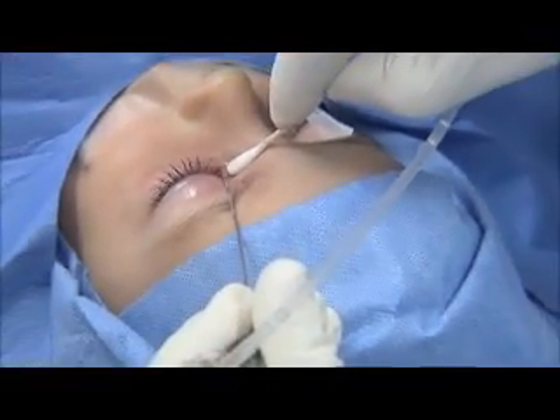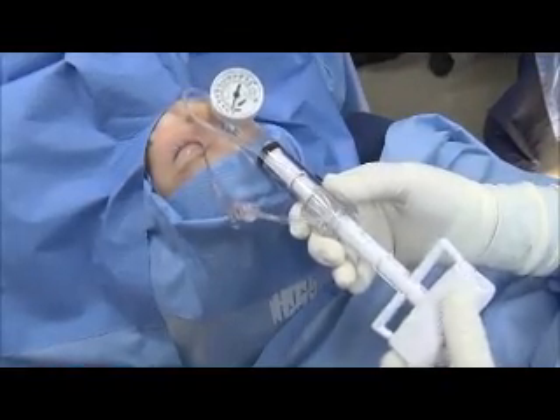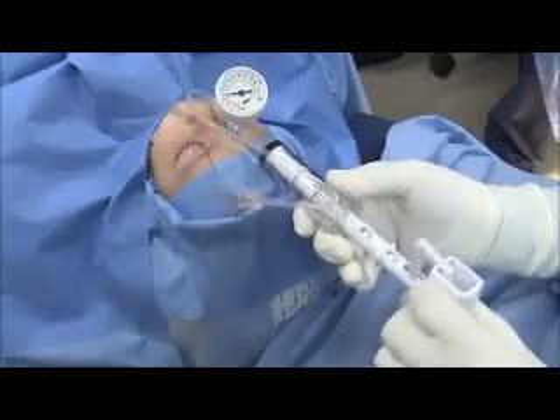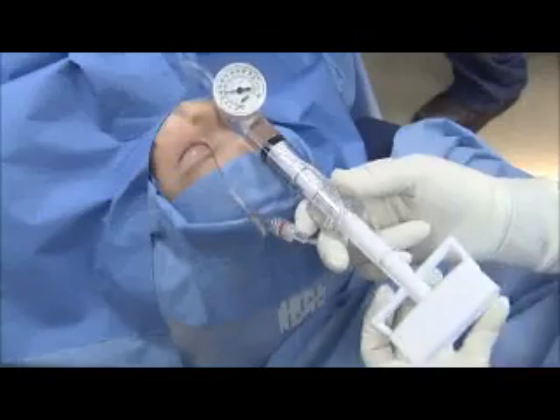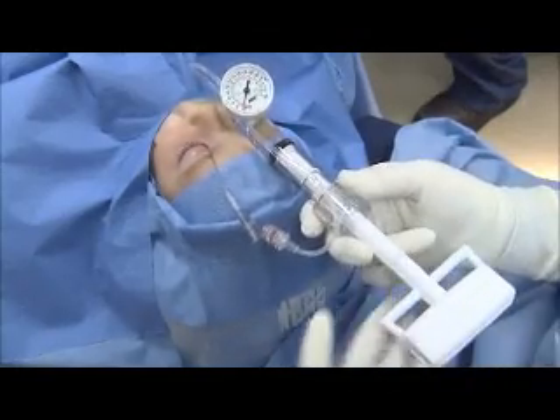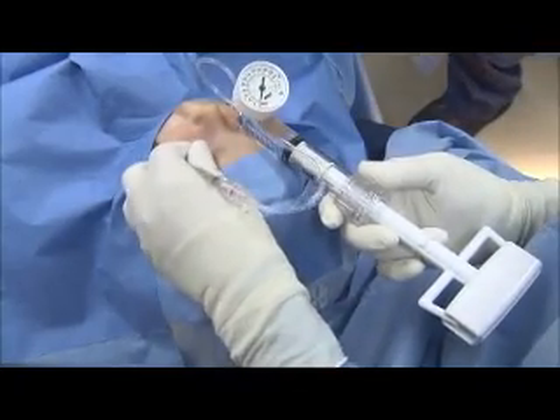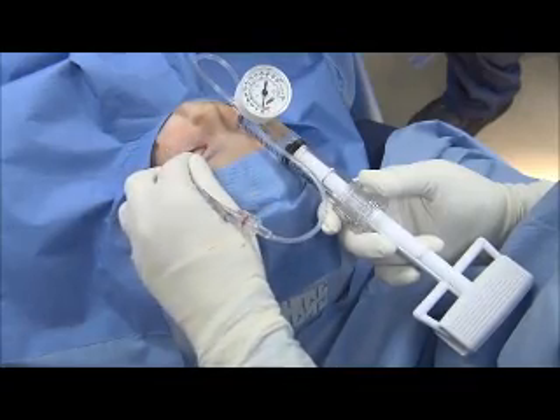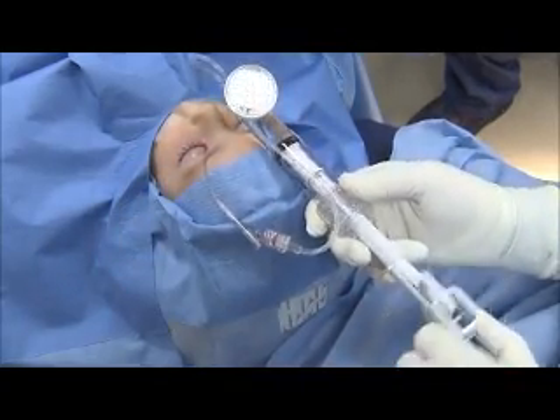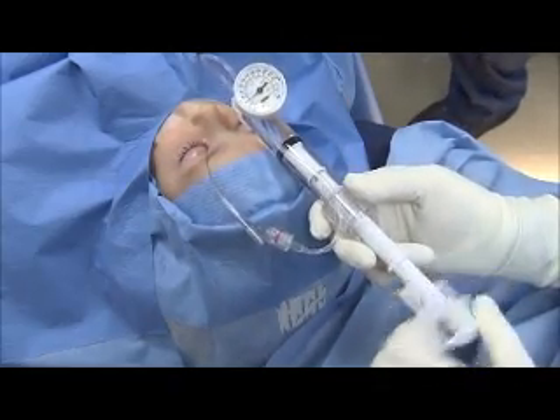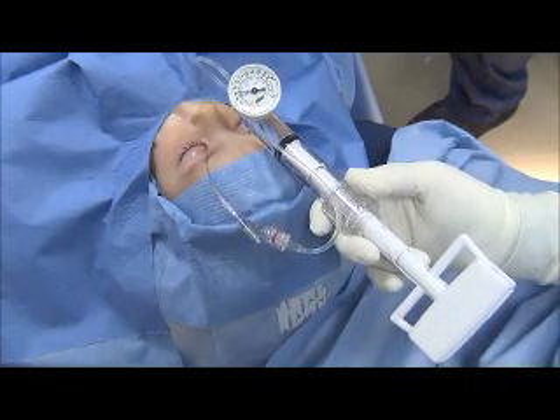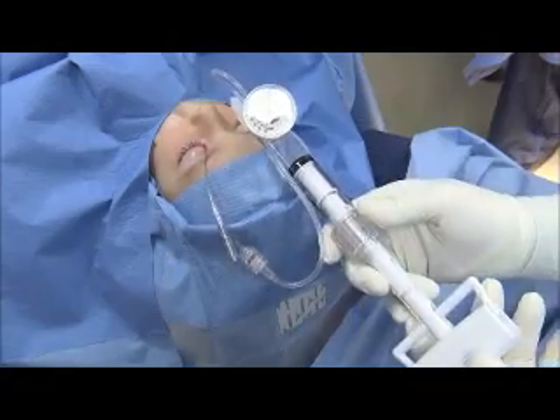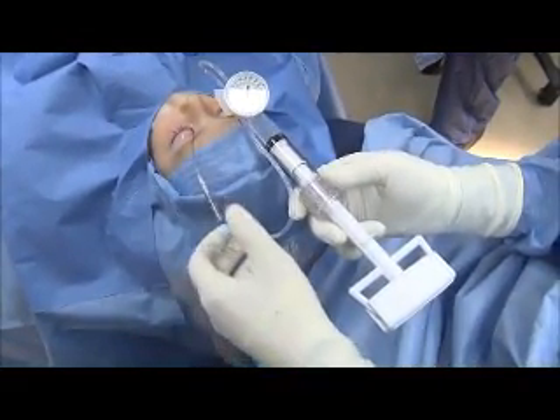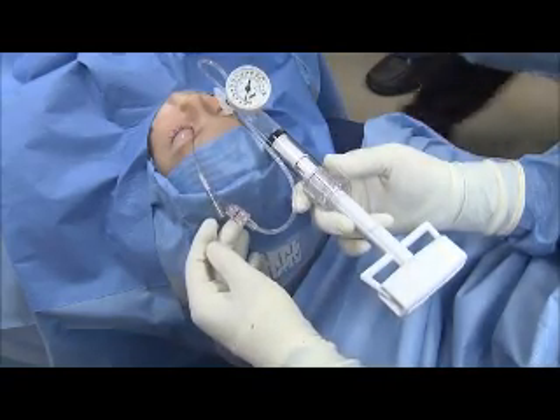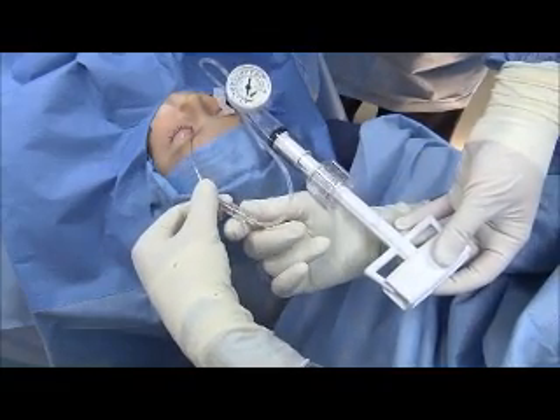So we're going to go ahead and inflate again to 8 atmospheres for 90 seconds. All right, we're going to turn this, go up to 8 atmospheres again for 90 seconds. All right, so now I'm going to deflate, pull the lever, and it goes to 0. I'll recheck our positioning, make sure it's just where I want it to be. And then we'll do another inflation to 8 atmospheres for 60 seconds. Okay, 60 seconds is up. We're going to deflate. So now we're going to disconnect the inflation device tubing.